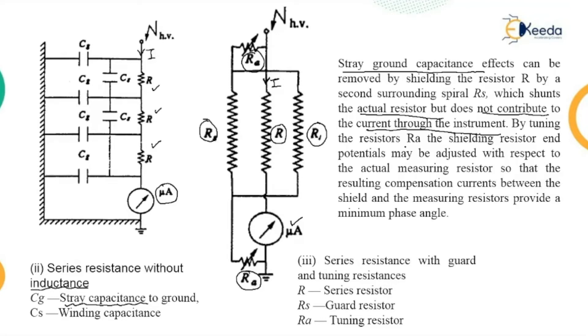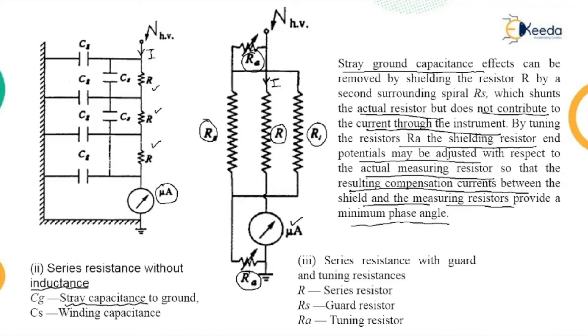By tuning the resistor RA, the shielding resistor potentials may be adjusted with respect to the actual measuring resistor, so that the resulting compensation currents between the shield and the measuring resistors provide the minimum phase angle. This is the circuitry used for measurement of current. The problem of residual inductance and capacitance seen in the impedance ammeter connection can be reduced partially using these circuits.